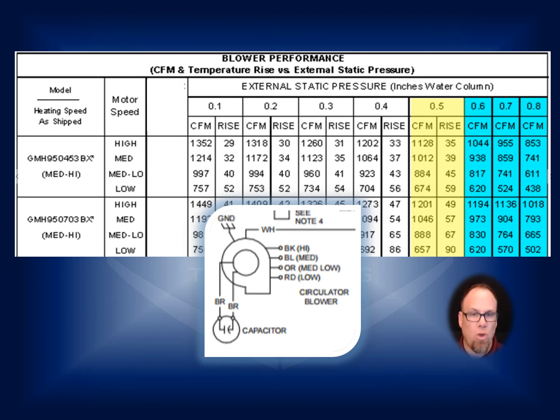And what we can do is, one, make sure that the filter is sized properly, and also make sure that it's not restrictive. The fiberglass filters, although nobody likes to use them because, well, you can hold it up like this and see right straight through it, and it's not going to catch much except for the big stuff. Well, you start putting more restrictive stuff in there, then it starts to cut into your airflow and mess everything up. So we can control the filter. We can control the filter both in size and restriction. We can control the return air drop.